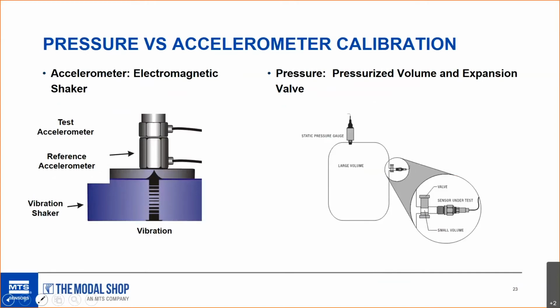On the accelerometer side, we have a vibration shaker, which creates vibration in, we assume, a perfectly vertical direction. On top, there's a stack of instrumentation, which has the test accelerometer sitting on top and the reference accelerometer below it, and they move in a back-to-back configuration to get a common vibration level between the two. Then we compare the voltage output, or the electrical output, of the two, knowing the precise sensitivity of the reference accelerometer to calibrate the test sensor.